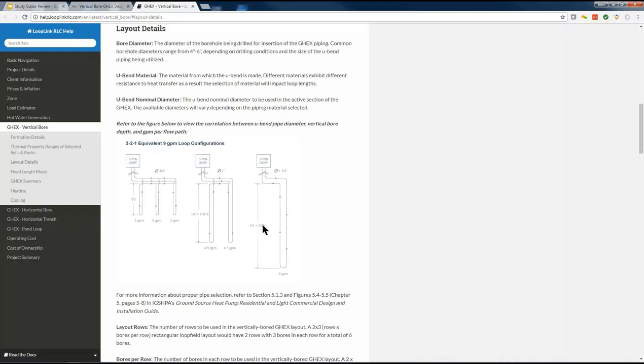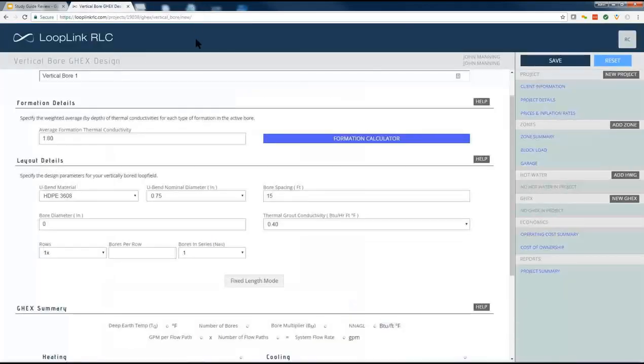And now, going to your 1.25 inch option right here, you want your 1.25 inch loops to represent about 2 to 3 tons of heat pump capacity. Notice that as your pipe sizes get larger, they get to be quite a bit more forgiving in that it takes less flow. There's a much larger gap between the minimum amount you need for turbulence and the maximum amount that you can accommodate before your head loss becomes a concern. So generally speaking, 1.25 inch loops are probably 2 to 3 tons, is what you're trying to accommodate in terms of flow rate with those.